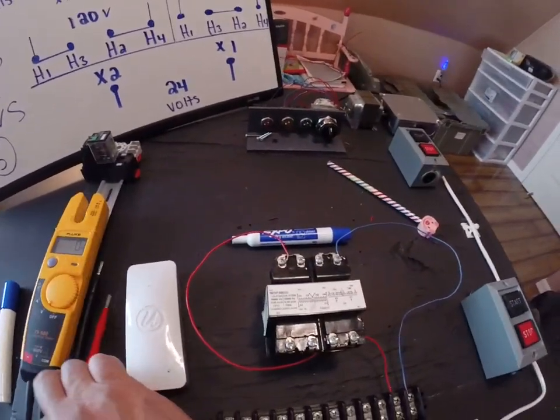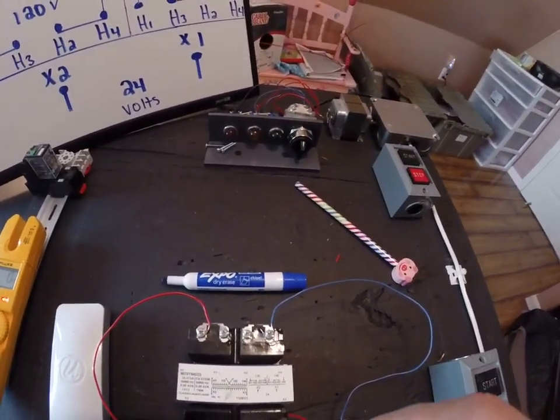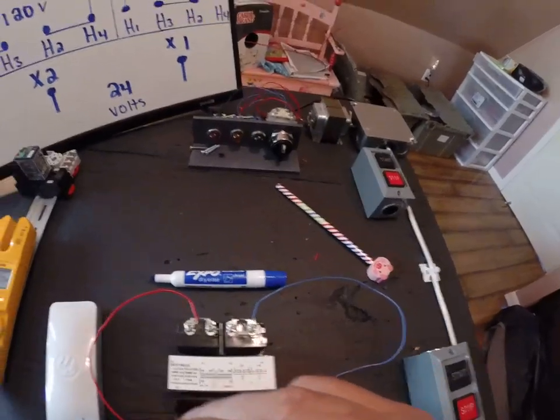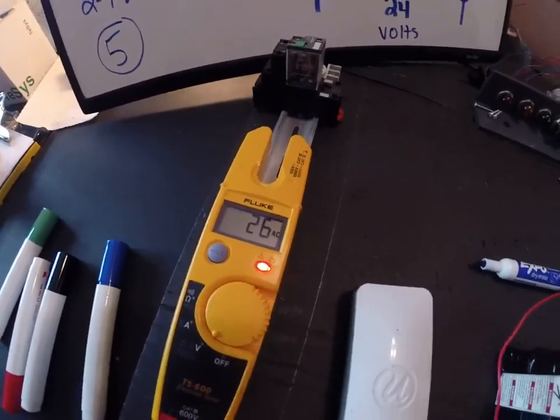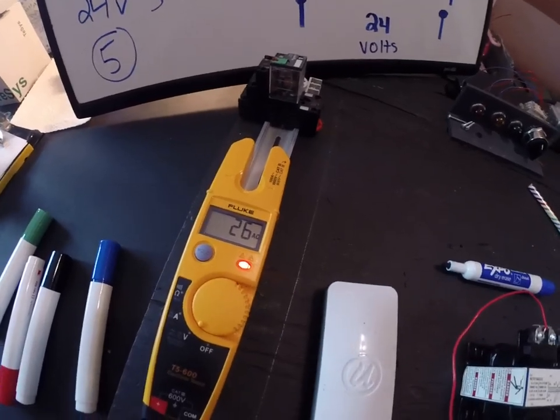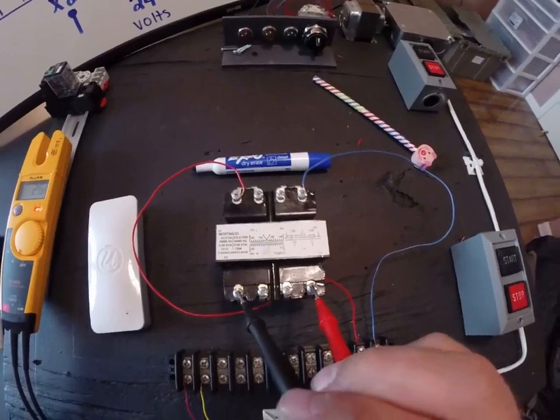So let's check our secondary voltage. I have to put one across X2 and another one across X1. And then check my voltmeter. And I've got a little bit high, 26 volts, which is okay. By the time you use it and have a little voltage drop, you'll be right back down to 24 volts. So pretty cool.